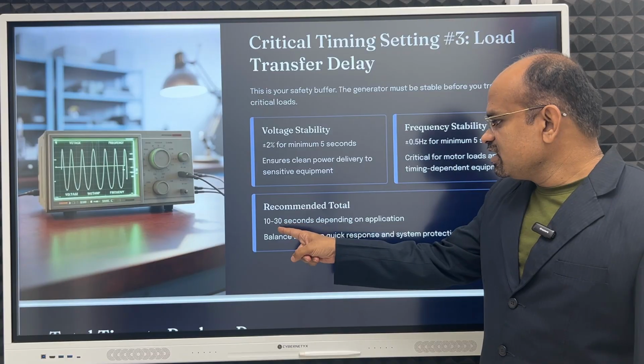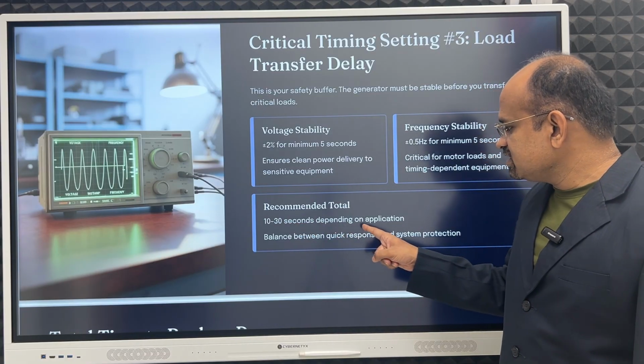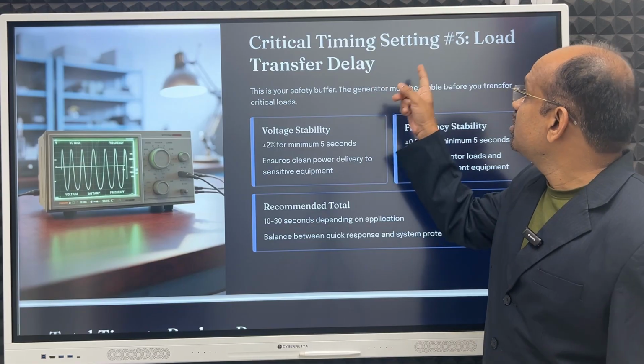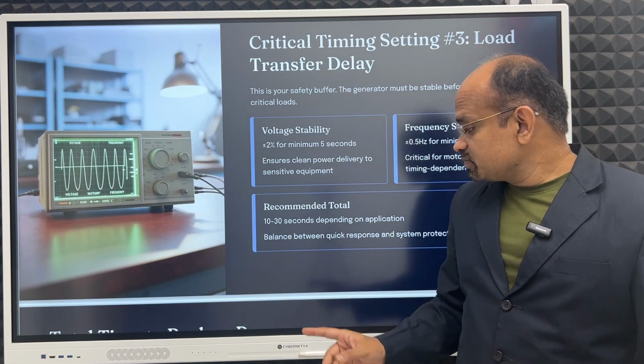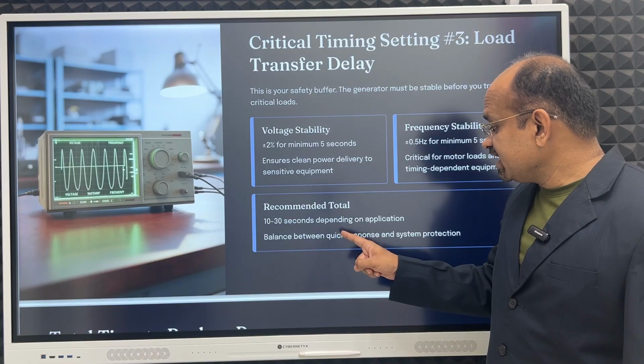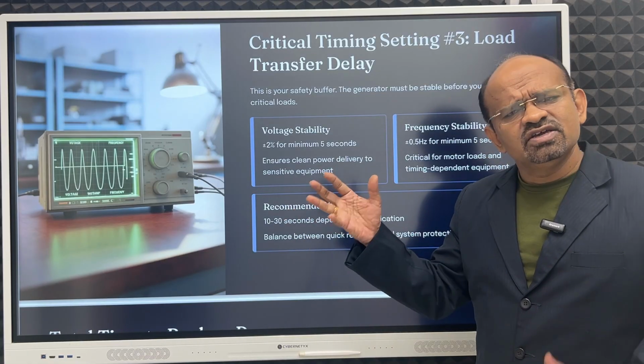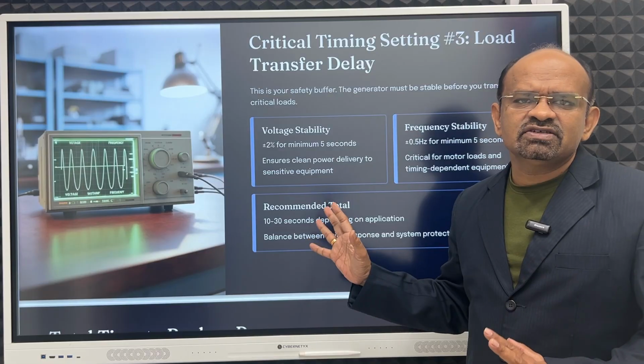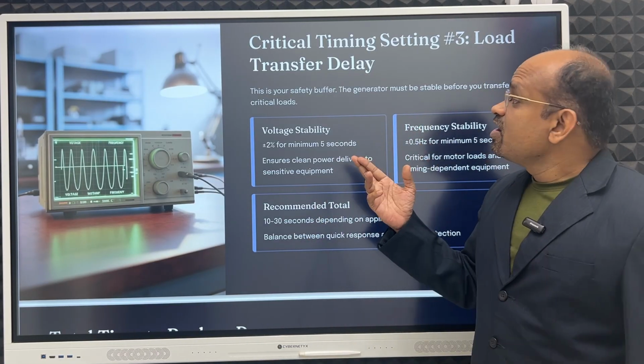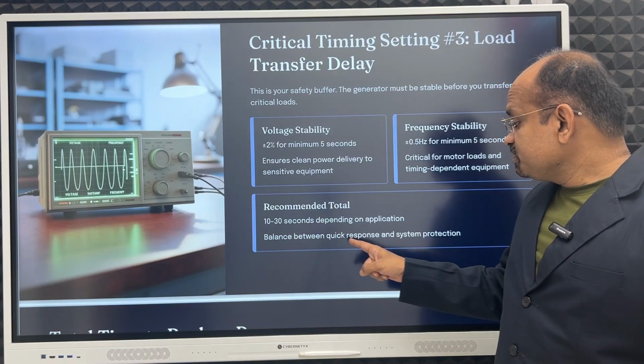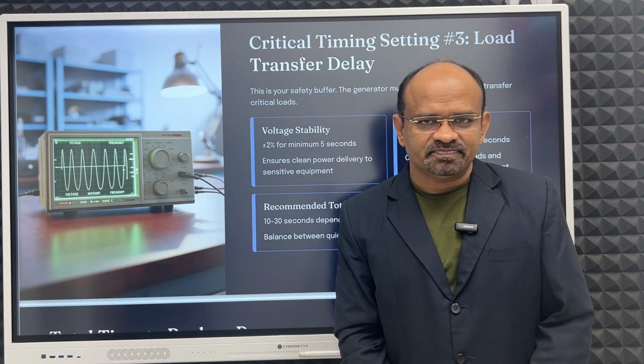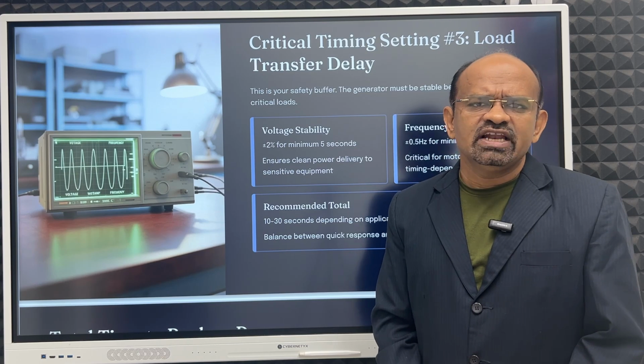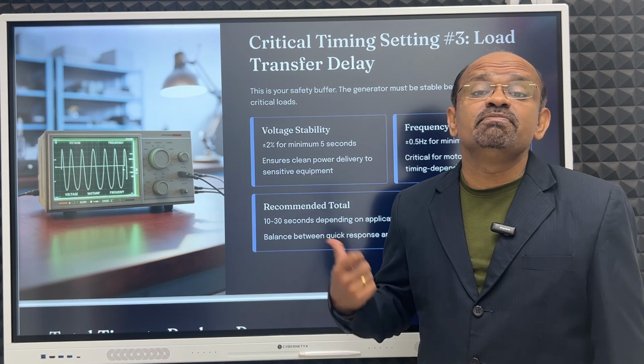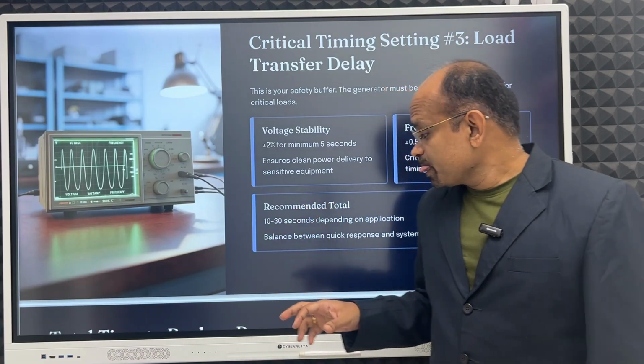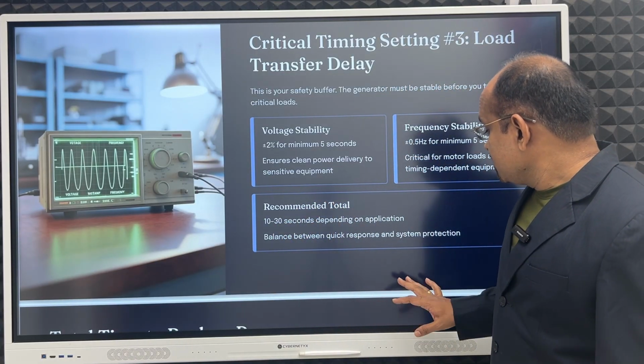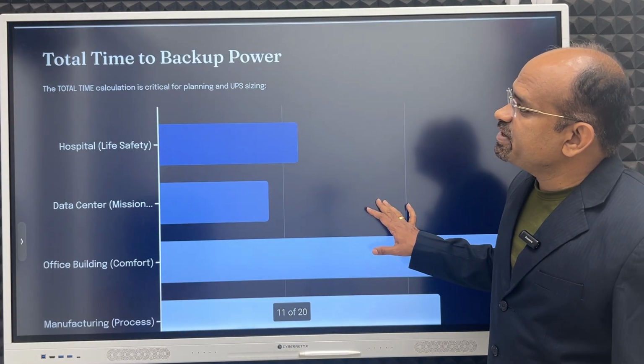Then the recommended total is 10 to 30 seconds depending on application. Total what? Load transfer delay. How much? 10 to 30 seconds depending on application. If it is critical, you can keep less. If it is non-critical like buildings or industry, you can keep even a 30-second delay for the load transfer. Balance between quick response and system protection. You should judge it as per the emergency or load type. Quick response and system protection entirely depend on that.